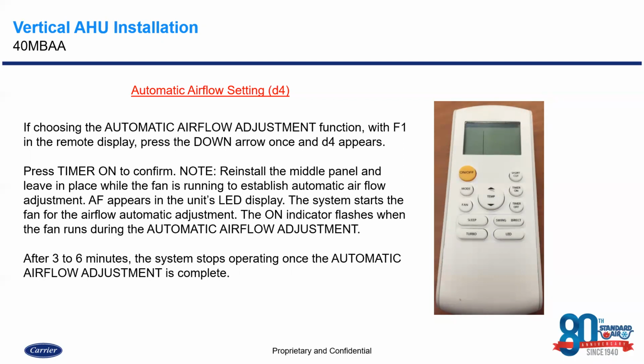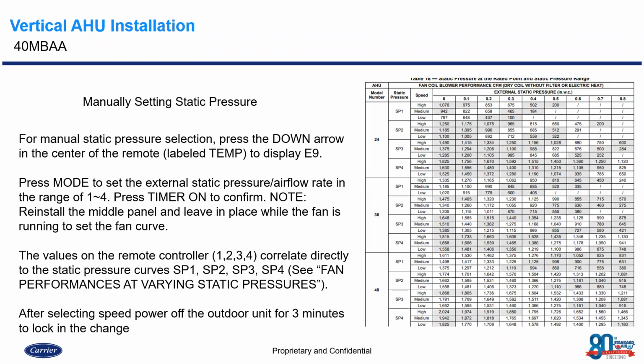Okay, now this is for the automatic airflow setting. If for some odd reason, because we don't live in a perfect world, this doesn't set up properly and you're not getting the correct amount of airflow to every zone, you also have the option of going into the static pressure setup manually. So what we're going to do is the same exact thing that we did to get into that advanced service feature on the previous slide, except now instead of going to that D4, we're going to navigate to our code E as in Eric, 9. So E9 on that wireless controller is what we're looking for.